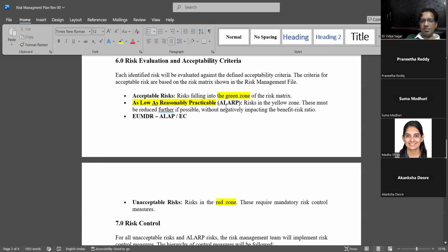If they are okay in yellow zone, they are as low as reasonably practicable, still they are risks. So you need to bring all those in red zone to green zone by risk controls. All the unacceptable risks in red zone, you need to bring them into green zone by using risk control options, risk control mitigation methods, and even those in yellow zone, you need to bring them into green zone. But some in yellow zone are accepted, but you need to give proper explanation.